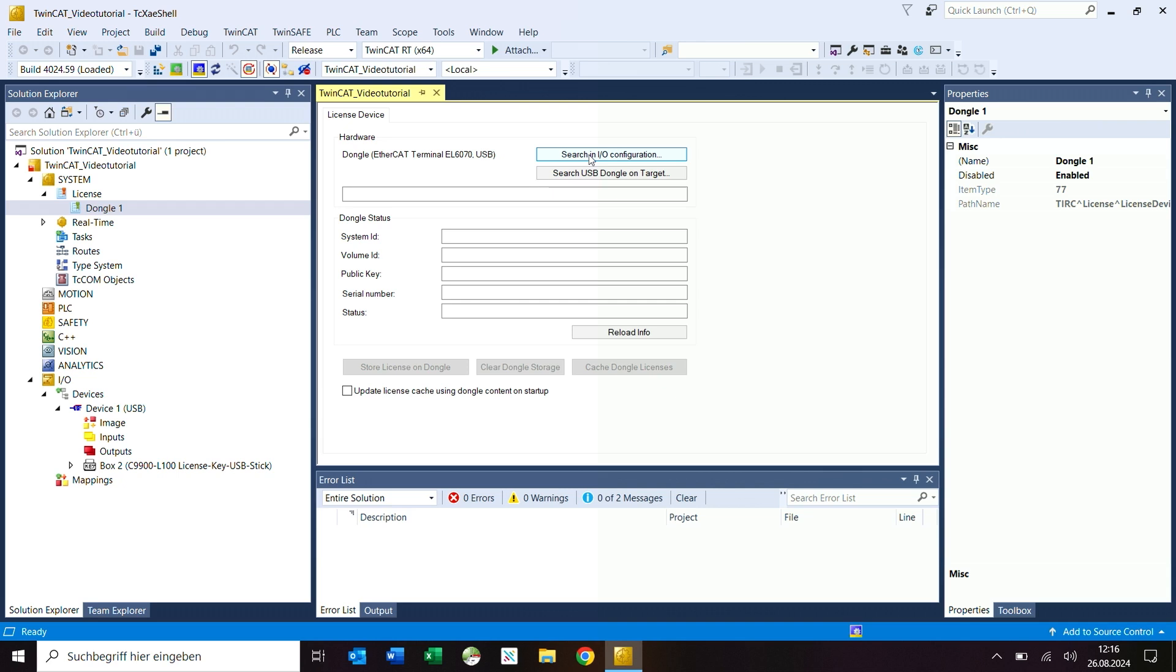An entry in the current config file is used to control that a license file that is not yet in the IPC license folder is automatically copied to the IPC license folder when TwinCAT runtime is started. A manual restart of the runtime is then required as this cannot be triggered automatically for security reasons.